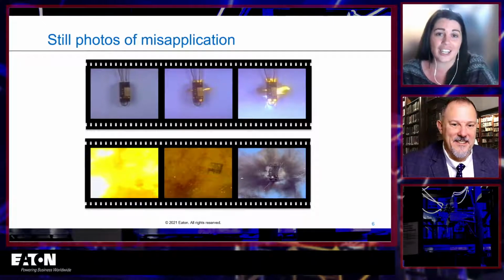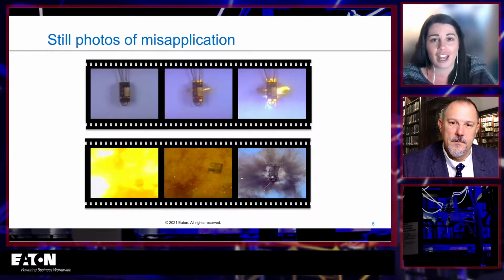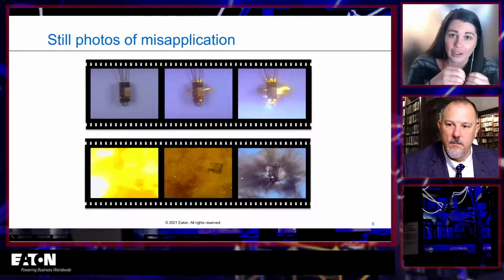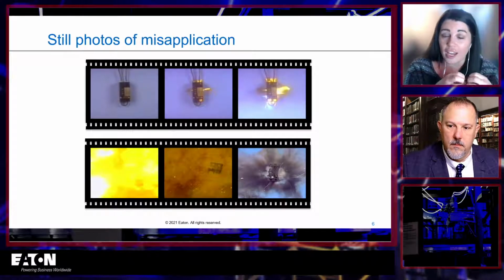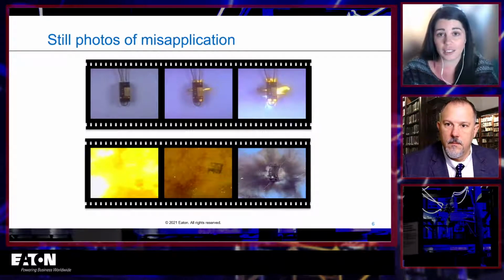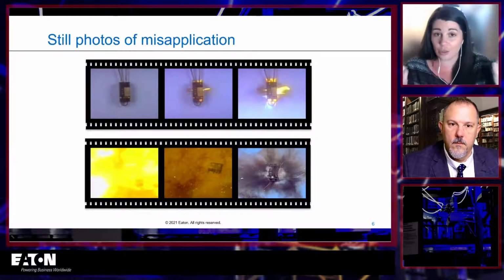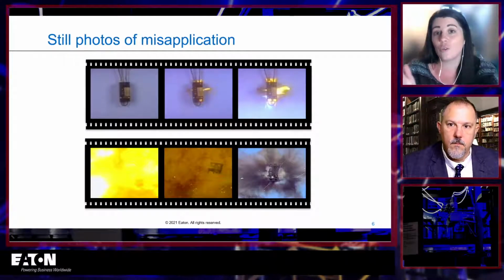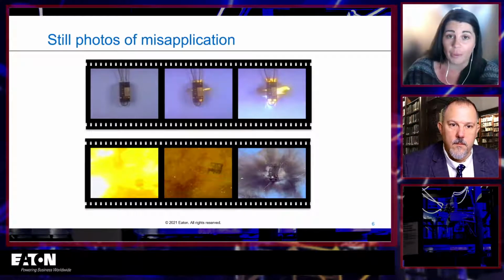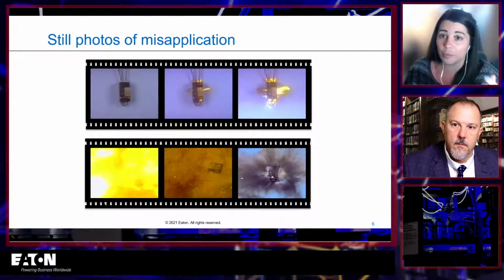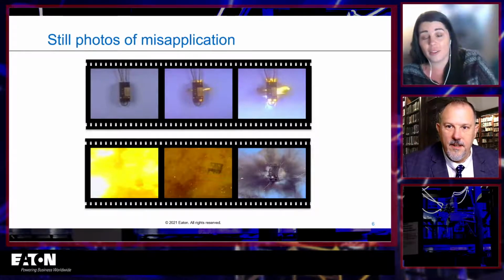Very important distinction. These still frames are fascinating because you can actually see this breaker knows that it's seeing too much current and it's trying to open. When it does that, it forms an arc between its contacts and tries to extinguish that through the arc chutes, but there's just too much energy for it to handle, and we get the rapid disassembly in the field, whatever it was you called it.